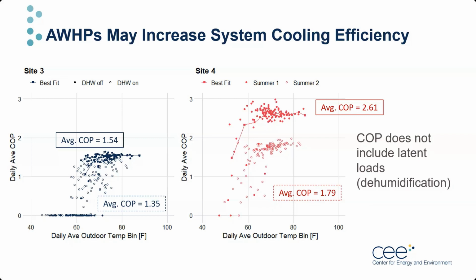with DHW enabled. Note that the configuration of these systems does not allow the unit to dump heat from cooling mode into the domestic hot water system. That might be one way to improve efficiency, but it would require significant system modifications.